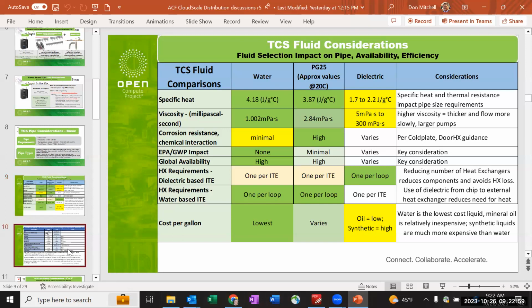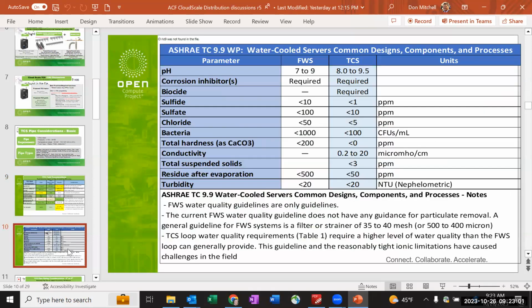But if you changed out your servers and went to a server with a microchannel cold plate in it, now you've got a different requirement on the quality of your coolant. In that case, whatever was circulating, you'd have a pump inside the cabinet circulating between your IT equipment and your rear door cooler. At that point, you would have to either add a filter or put a better filter in to meet the requirements of the cold plate.